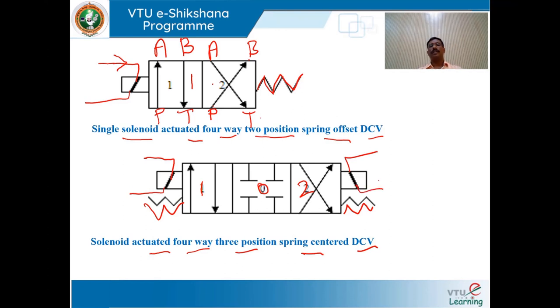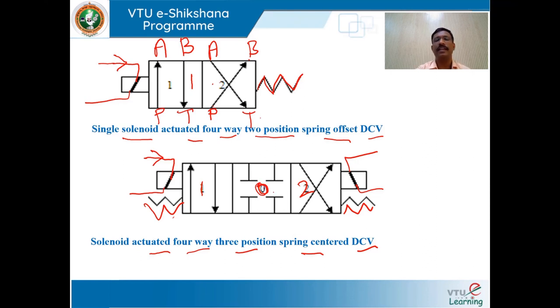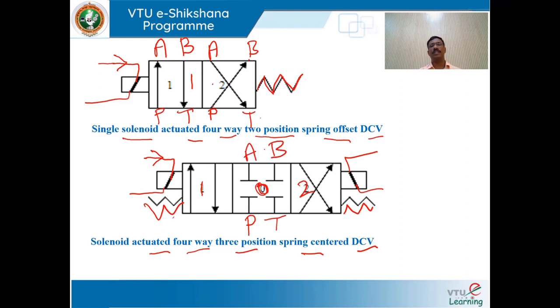When there is no current or the coil is not energized, the valve moves to the center path configuration due to opposing spring forces and all ports are closed. P is connected to the pump line, T to the tank line, and output ports A and B are shown.